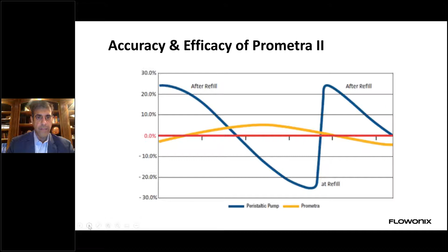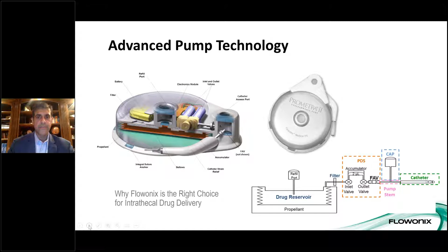Let's take a look at the inner workings of the pump. First off, there is a 20 ml pump and a 40 ml pump available. Both of these are similar in design. There is a propellant, which is really the driving force pressurizing the drug reservoir to 22.5 psi. This basically pushes the drug out of the reservoir through a filter into what is called the precision dosing system, or PDS. Basically, medication goes through the inlet valve into a dosing chamber, which holds about 2 microliters of drug. This chamber is pressurized to 12 psi. Once 2 microliters of drug accumulates in the dosing chamber, drug is then forced through the outlet valve, through the flow activated valve, out the pump stem, and out the catheter. And it's pushed out the catheter with a forceful exit velocity 6,500 times that of the peristaltic pump. Next slide.